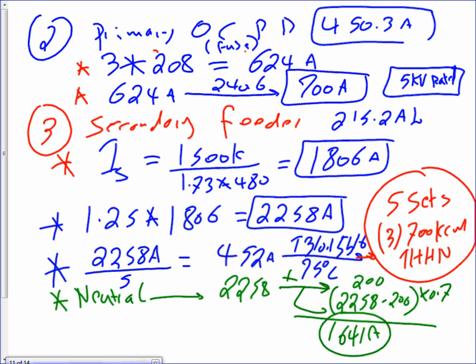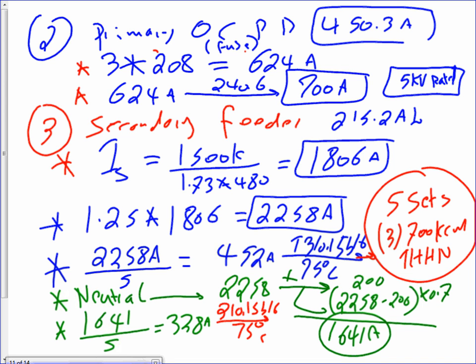And then take the 1641 divided by 5, because we also have to parallel them. That will give you 328 amps. And from here, take it to 310.15 B16, 75-degree column. That will get you 5 sets of one conductor, 500 kcm THHN.